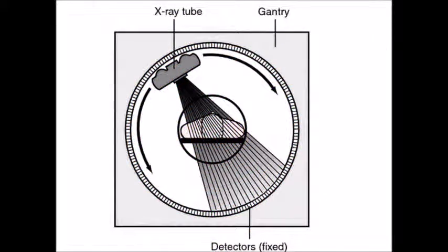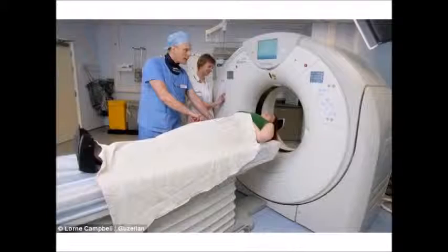X-ray slice data is generated using an X-ray source that rotates around the object. X-ray sensors are positioned on the opposite side of the circle from the X-ray source. An X-ray tube and detector are physically rotated behind a circular shroud. Newer machines permit continuous rotation with the patient to be imaged slowly and smoothly slid through the X-ray ring. These are called spiral CT machines. A subsequent development of the spiral CT was multi-slice CT. Instead of a single row of detectors, multiple rows of detectors are used effectively, capturing multiple cross-sections simultaneously. This is what it looks like inside that ring.